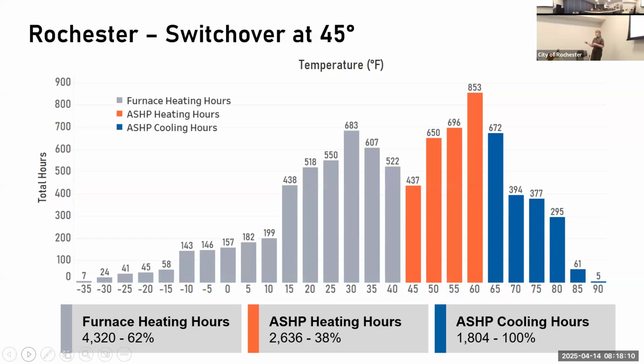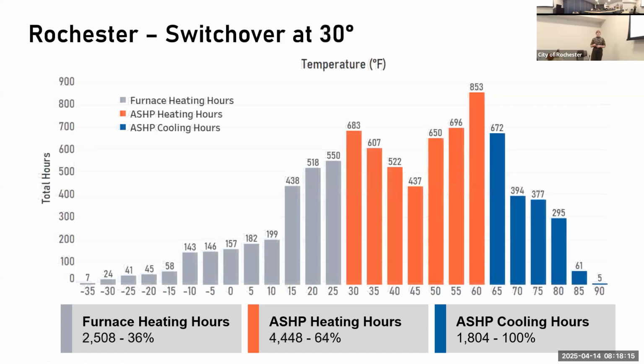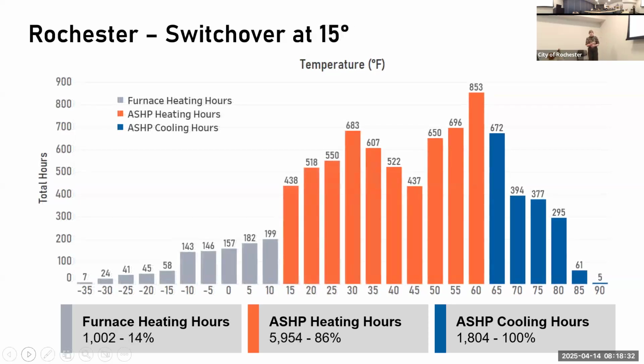If you're thinking about a furnace, even if it's modulating, one of those brand new 96% efficient ones, even if it's sized to support this, operating in all of this range it's going to be short cycling, because the lowest possible BTU output is still way more than the heating load needed for the home. So going back to the customer piece with natural gas, even with a higher switchover temperature of 35, 40 degrees, you're still saving that furnace from short cycling for a lot of hours throughout the year, which extends the life of the furnace and helps the customer be more confident it's not going to burn out from short cycling too much.